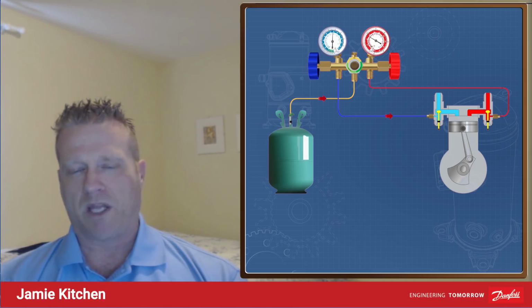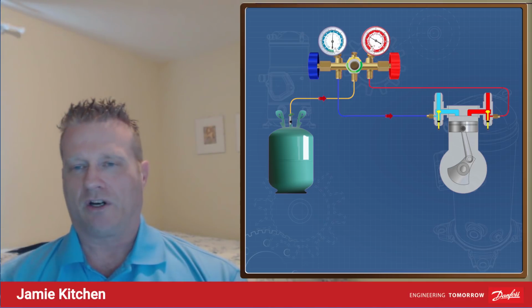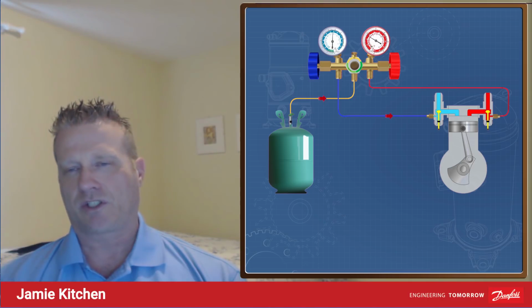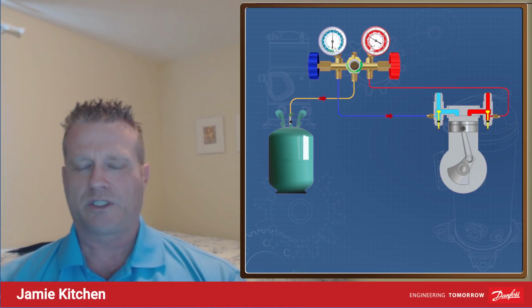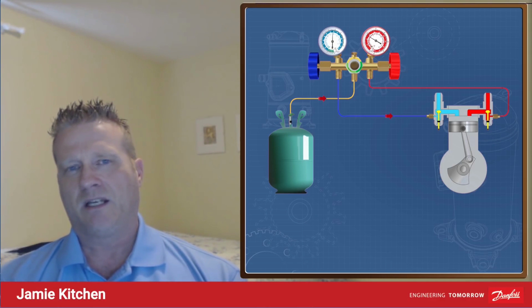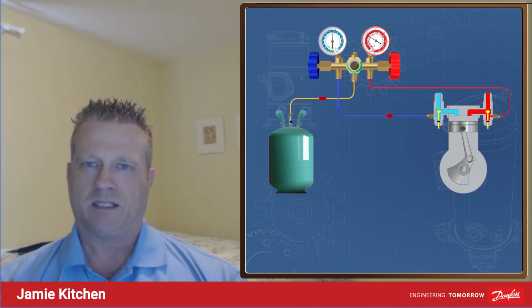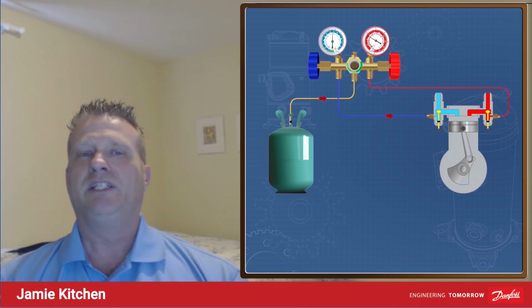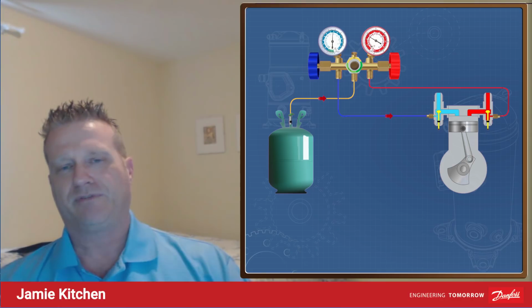So go by the manufacturer's specs. Get yourself some good thermistors or whatever you need on your meters. Measure and charge. If it's a TXV system, charge according to subcooling. You can measure your indoor and outdoor pressures. You know what your wet bulb's going to be inside. Measure all these things and charge it correctly. It's not going to take you a ton more time. And if it's done correctly, again, you've eliminated a major cause of systems failing.